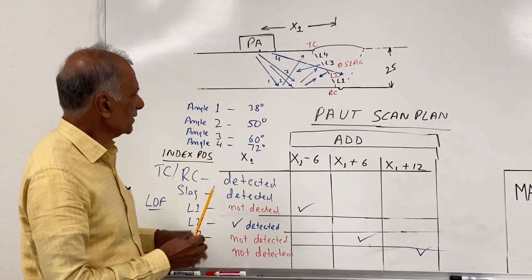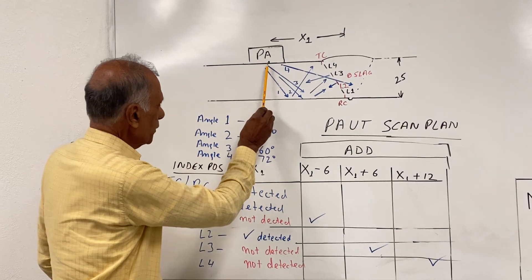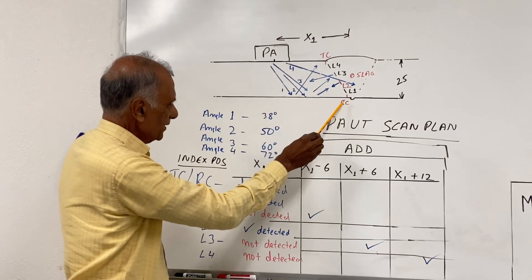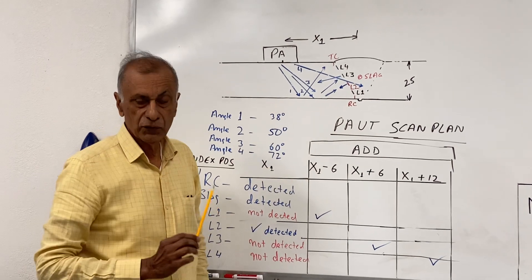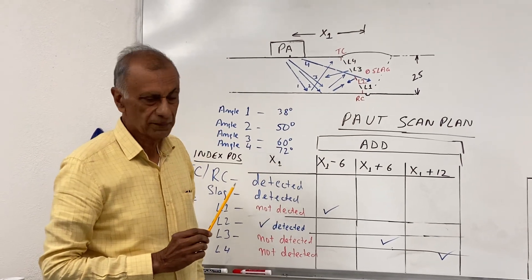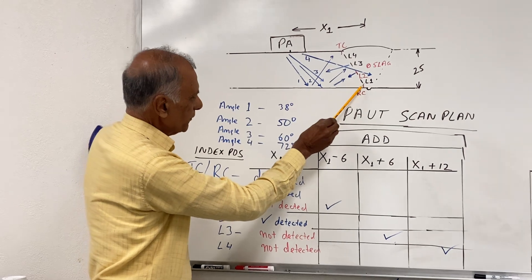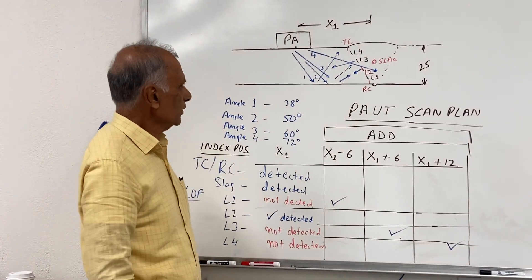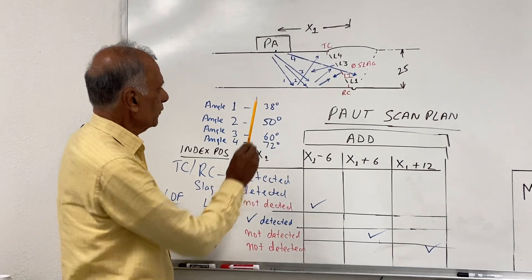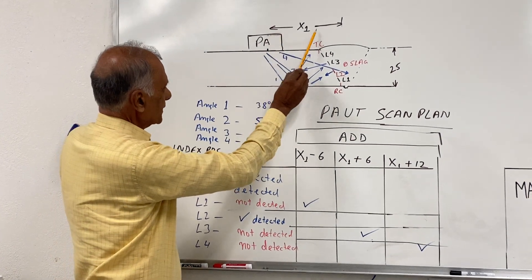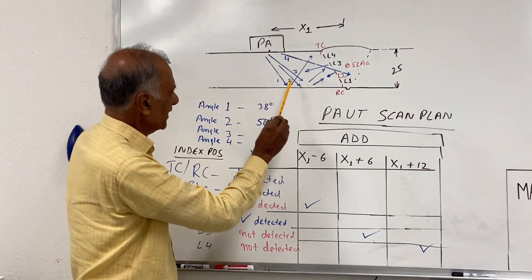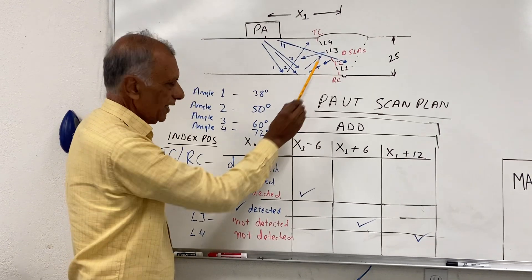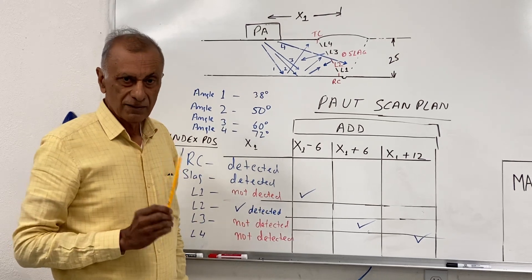The issue is that if you just keep the probe here at the X1 location, then the issue is with the detection of the lack of fusion flaws. I've shown here four lack of fusion flaws, L1, L2, L3, and L4. Now if I do a scan plan with one offset setting, which is X1, then according to this setup, all I will see is the L2 lack of fusion, because remember the sound, when it is incident on lack of fusion which is a planar flaw, will reflect back.